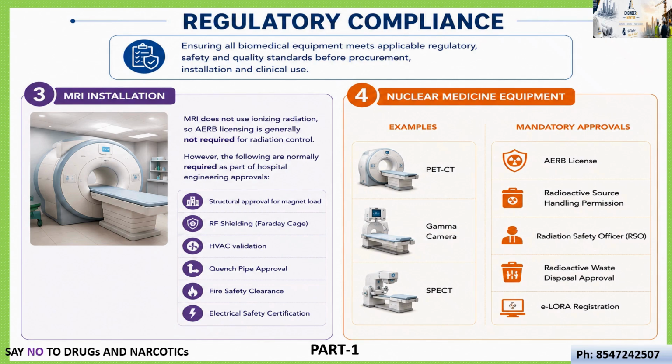Coming to the next category, nuclear medicine requires AERB approval in various stages, PET-CT, SPECT and gamma camera, etc. All require AERB approval, and radioactive waste disposal approval is required. Now, ELORA registration means e-licensing of radiation application.